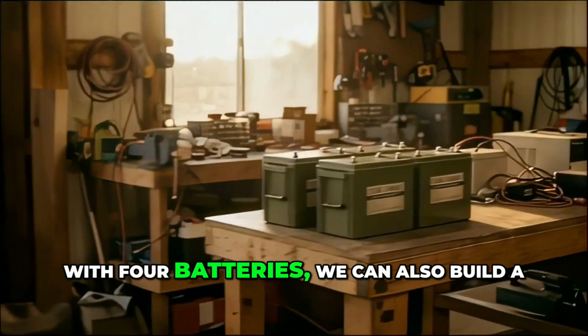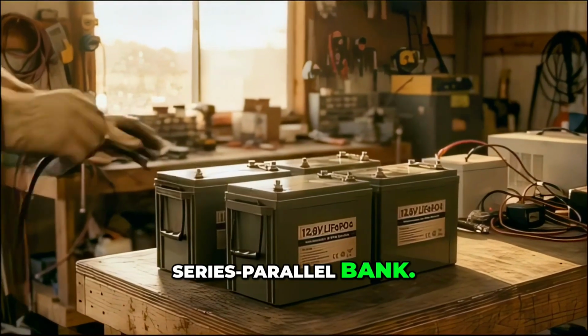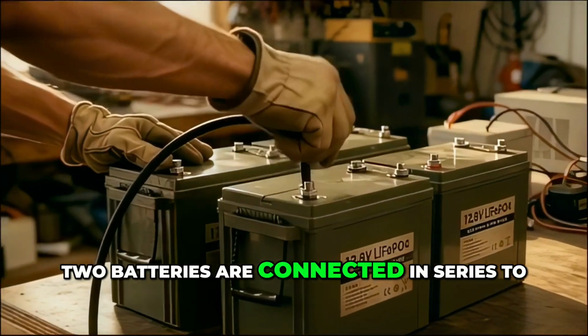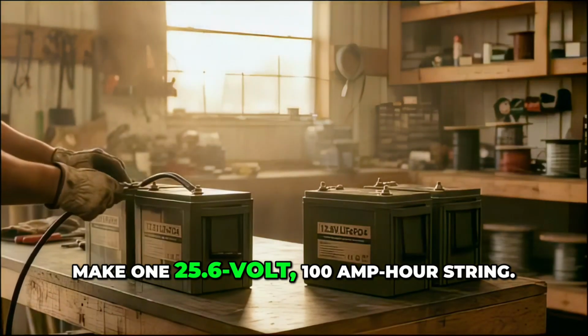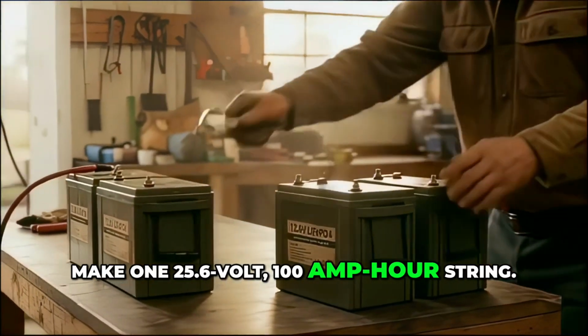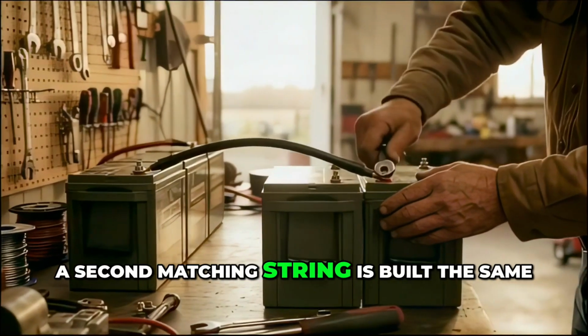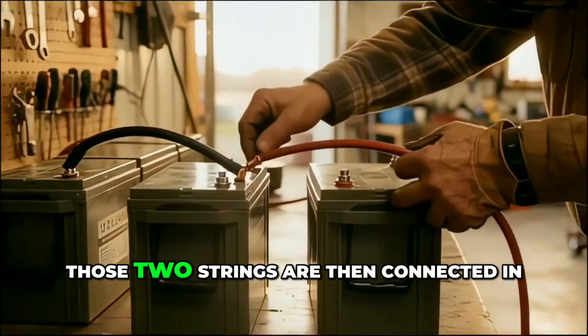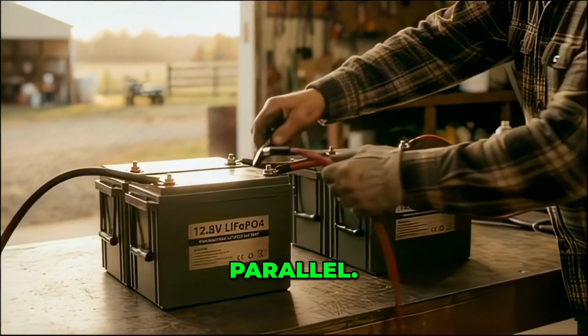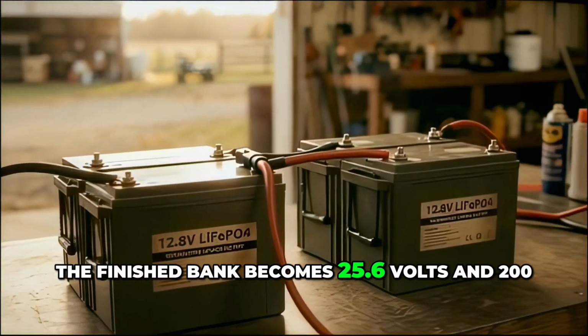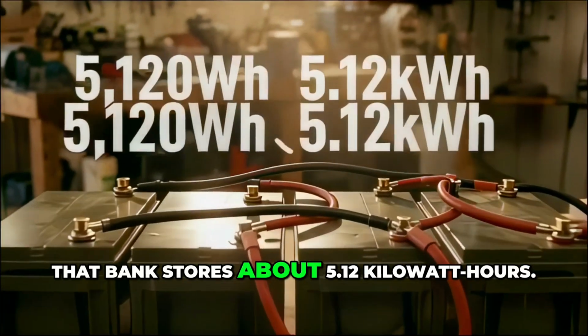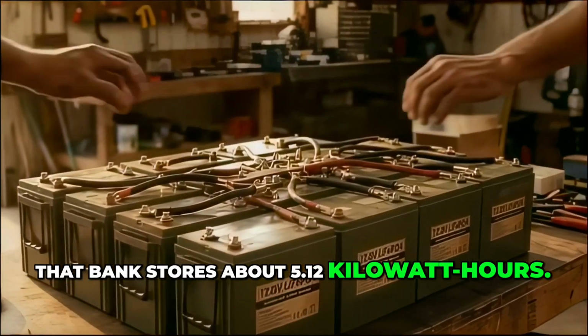With 4 batteries, we can also build a series parallel bank. 2 batteries are connected in series to make one 25.6-volt, 100 amp-hour string. A second matching string is built the same way. Those 2 strings are then connected in parallel. The finished bank becomes 25.6 volts and 200 amp-hours. That bank stores about 5.12 kilowatt-hours.